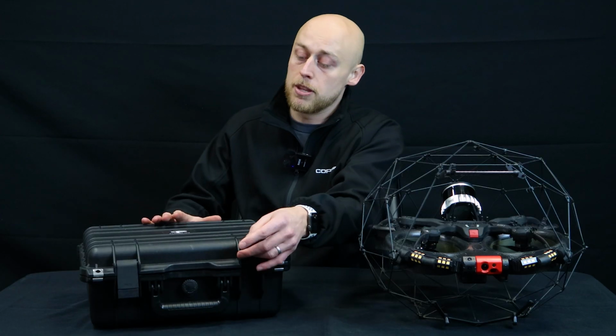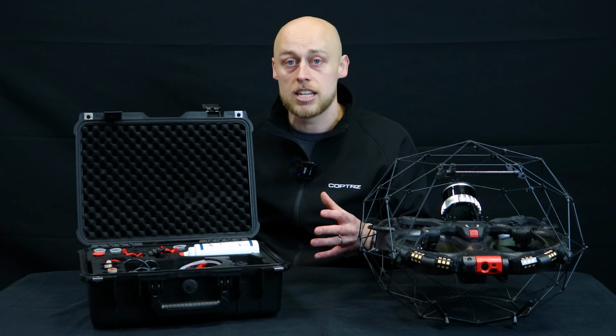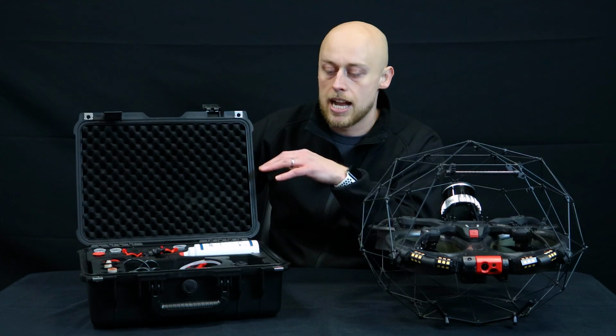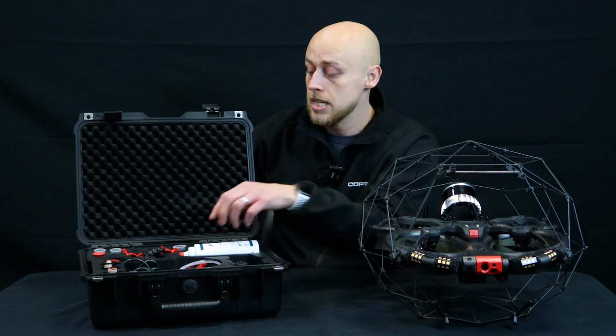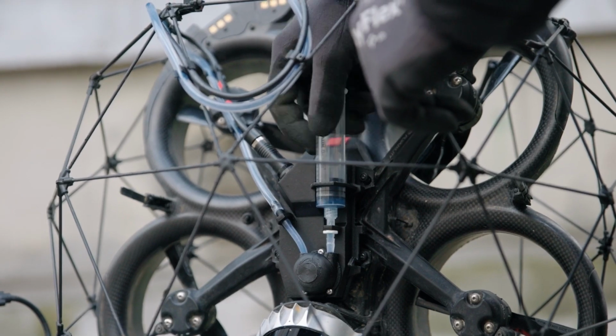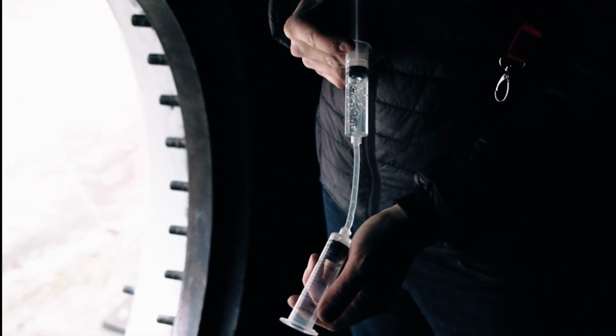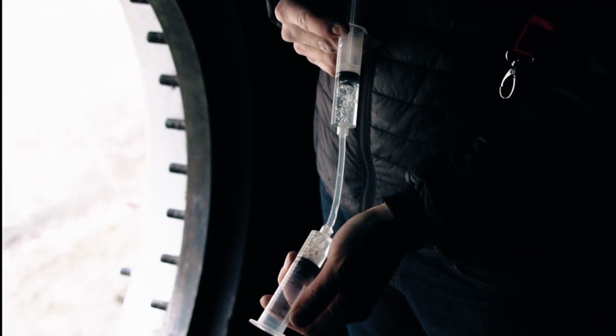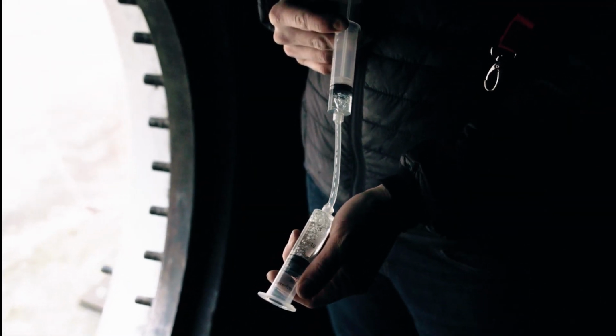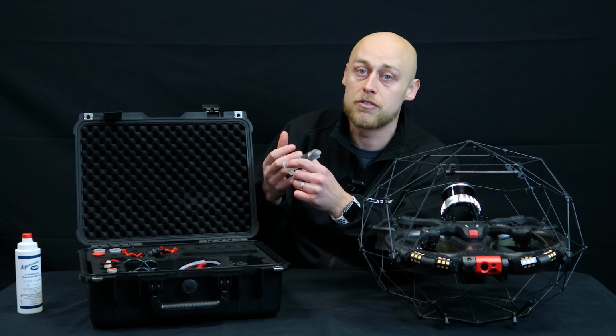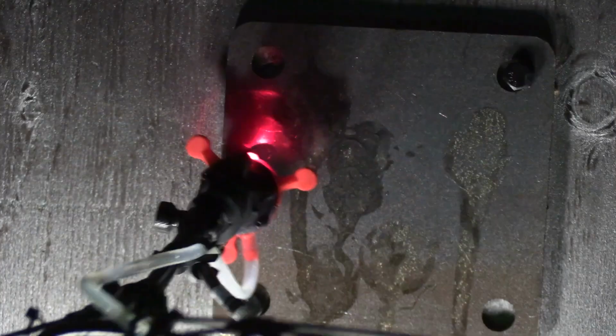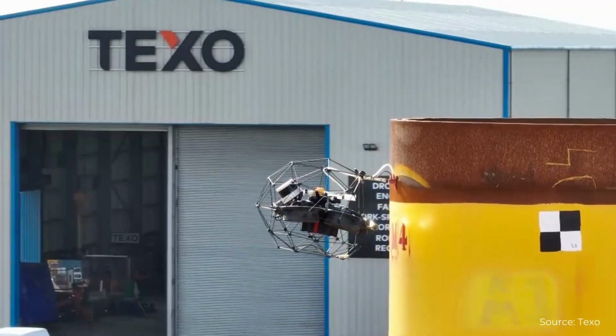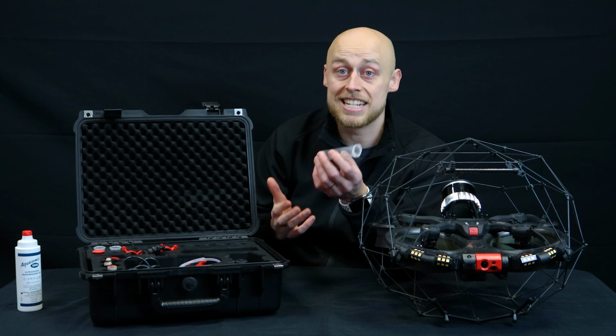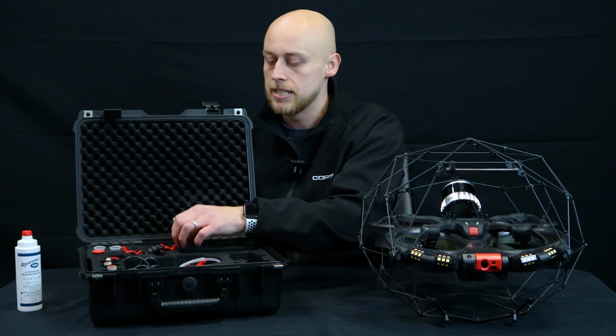So without further ado, opening the box, the system, the UT element, comes in this really great carry case, all marked out with where things are supposed to go. We'll start with the couplant itself, essentially a lubricant to allow for the syringe, which we have here, to attach to the top of the drone. And what that will do, via a button on the controller, it'll push through that lubricant to the face of the UT arm, which will give essentially a liquid at the front of the probe arm, which will take away all of the dust and the air bubbles between the actual surface of the probe and the surface of the asset, making sure that you've got more detailed and accurate responses to that data.